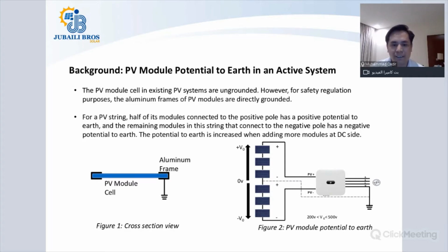As you can see in this picture on the right side, there are 6 PV modules. Half of these have negative potential to Earth, and the other half on the positive side have positive potential to Earth. Normally, these potential differences in low voltage string inverters are between 200 to 500 volts.